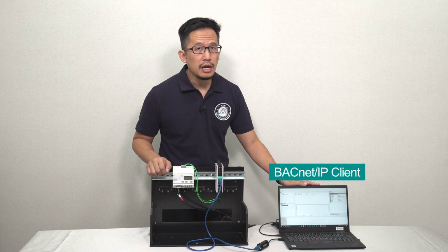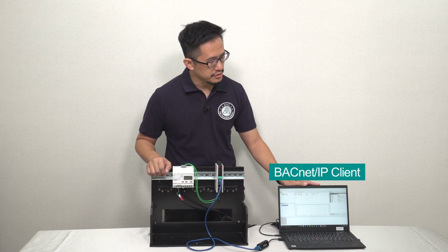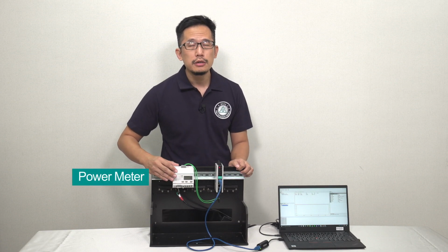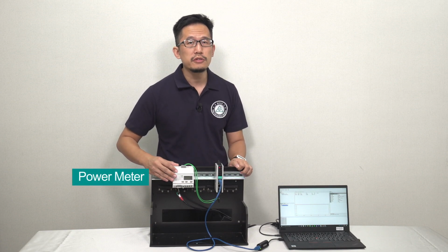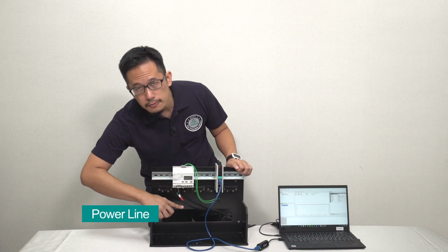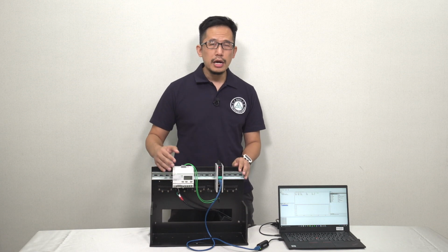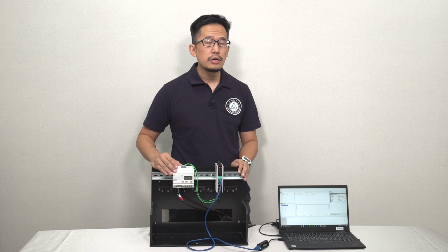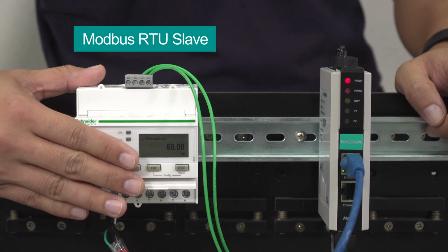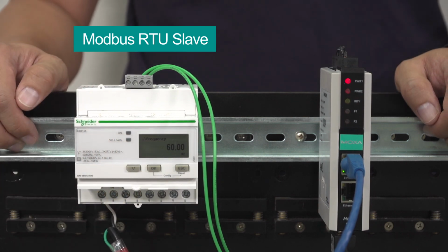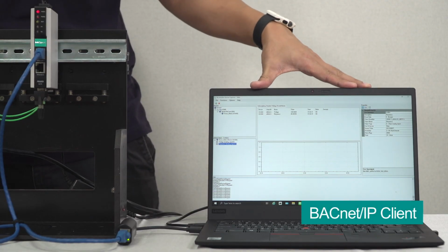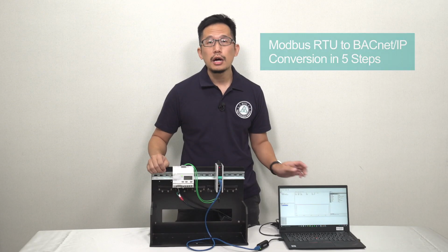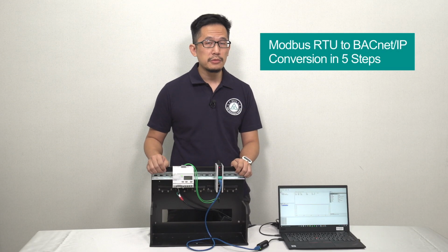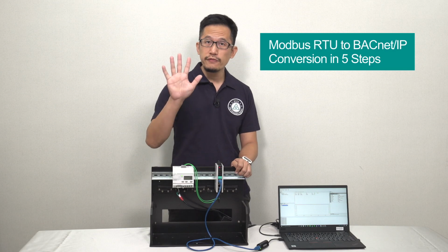Here, we have a BACnet IP client simulator running on this PC, and we have a power meter that measures the usage and the quality of the power coming through this power line. To connect this power meter to our BACnet IP network, we have to convert Modbus RTU protocol, which the power meter uses, to BACnet IP protocol, which our BACnet IP client uses. I'm going to show you how to set this up with the MGate 5217 in just 5 steps.